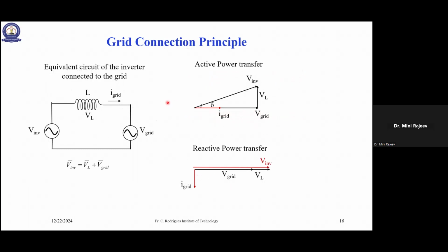Before going to the control, I will tell you the grid connection principle. This is the equivalent circuit of the PV inverter connected to the grid, not necessarily a PV inverter, any inverter for that matter. In our case, we will consider this as a PV inverter. Now, we cannot connect 2 different voltage sources in parallel; we need some energy storage in between. So here I am showing an inductor. There is an inverter, an inductor, and a grid voltage. The inverter voltage will be the phasor addition of VL, the inductor voltage, and the grid voltage.